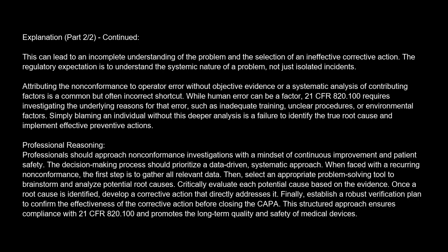Attributing the nonconformance to operator error without objective evidence or a systematic analysis of contributing factors is a common but often incorrect shortcut. While human error can be a factor, 21 CFR 820.100 requires investigating the underlying reasons for that error, such as inadequate training, unclear procedures, or environmental factors. Simply blaming an individual without this deeper analysis is a failure to identify the true root cause and implement effective preventive actions. Professional reasoning.